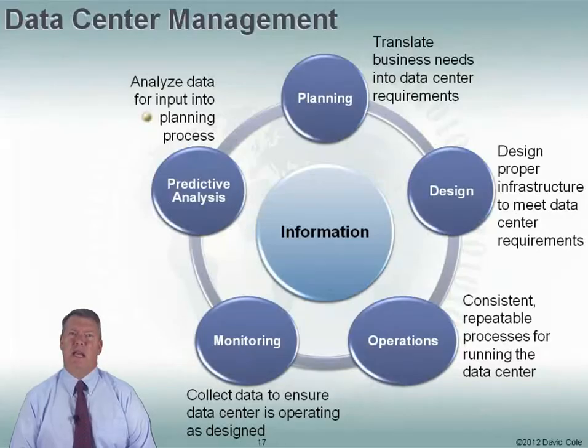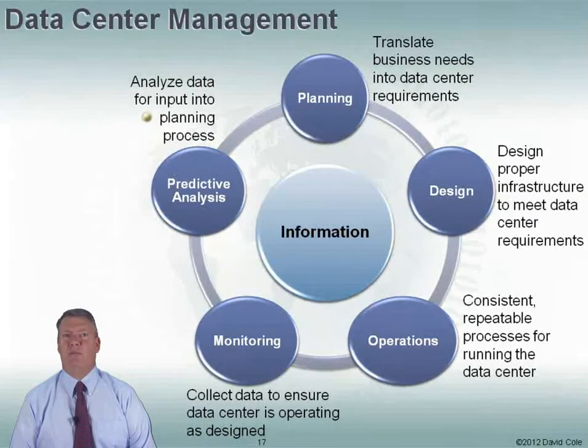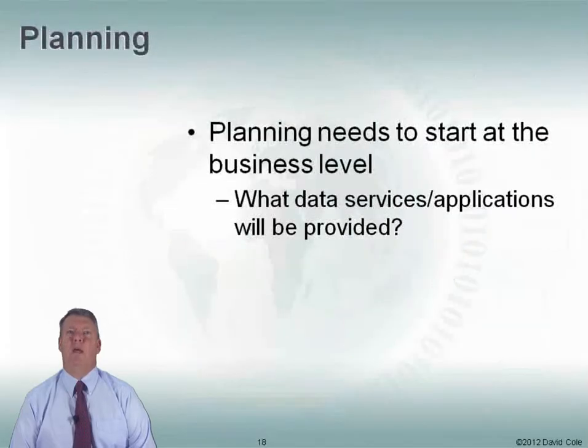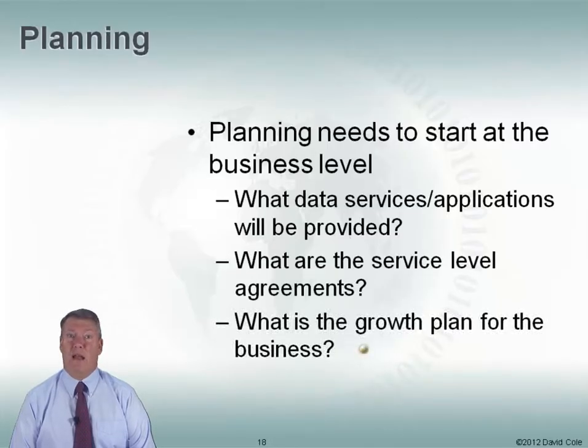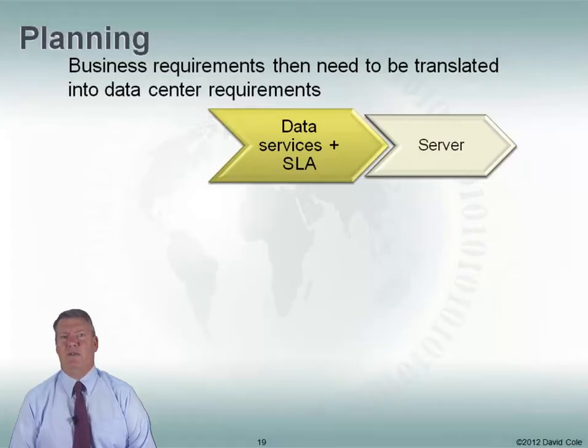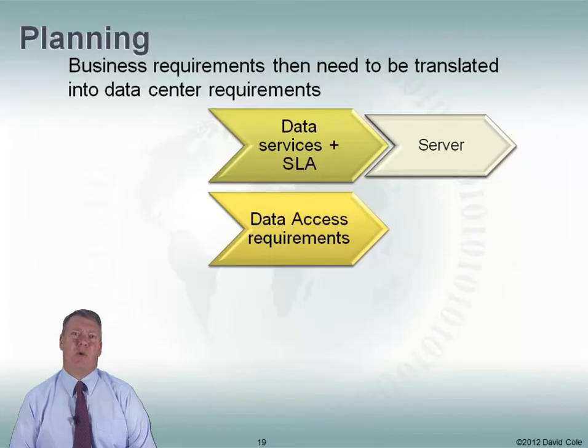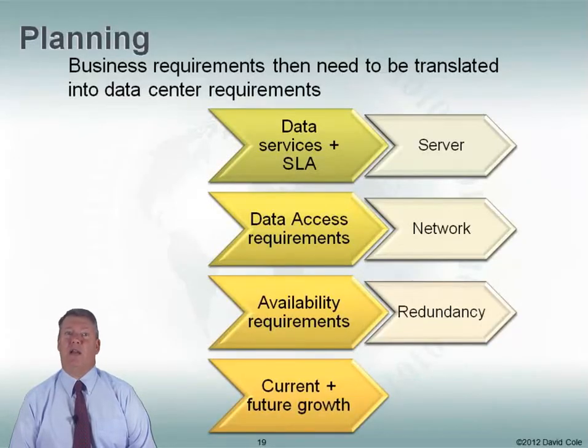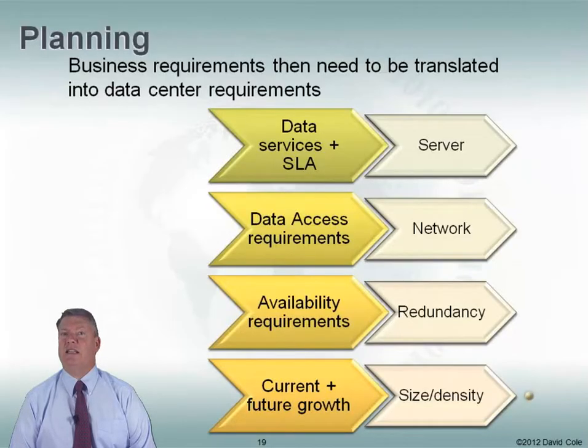What's important to know is that in the middle of that circle is information. We need everyone to have a single source of truth. If the planning group is using one piece of information, the monitoring group another, and operations using something else, we're going to have a hodgepodge of information. On the planning side, planning always starts at the business level — what applications are we going to provide, what are my service level agreements, what's my growth plan? The planning side is about translating these into data center requirements. Services and SLAs help define what kind of service I need; data access requirements help define my network requirements; availability requirements help define what kind of redundancy I need; and current plus future growth helps define the size and density of my data center.